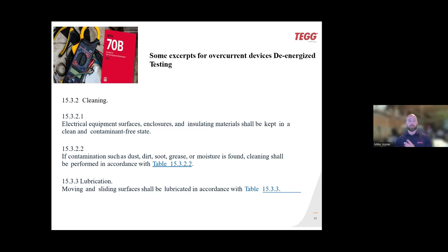You want to go to the next one? So this jumps in real quick as to what kind of testing is done while we're on site for the de-energized maintenance, with the primary and secondary injection testing. We do measuring and ducter testing and ensure that all the breakers are working properly and exercising, per manufacturer spec. Sometimes they talk about primary and secondary injection testing, which is what this table includes.